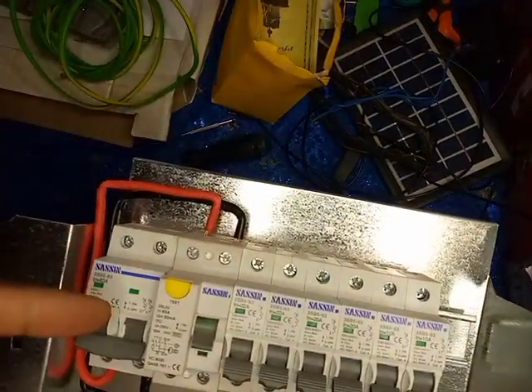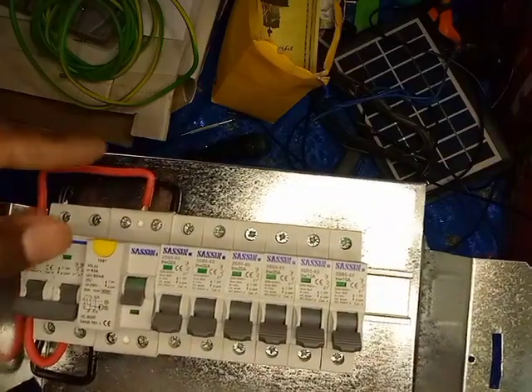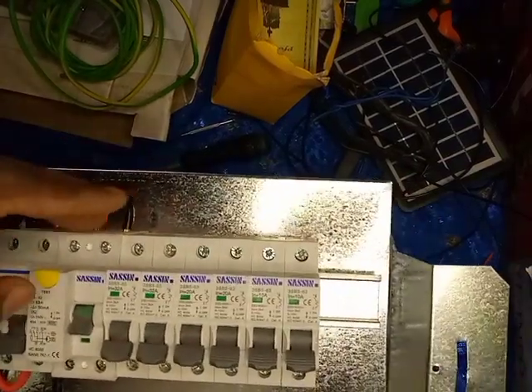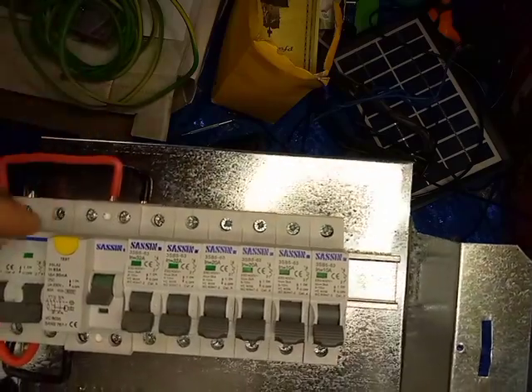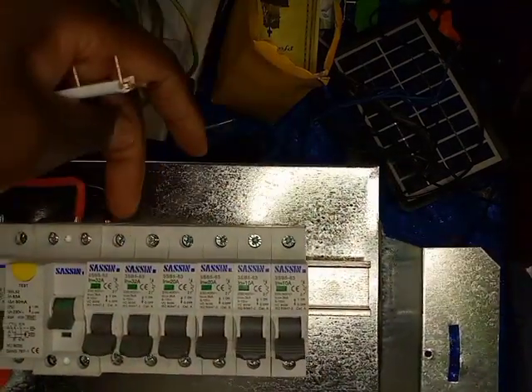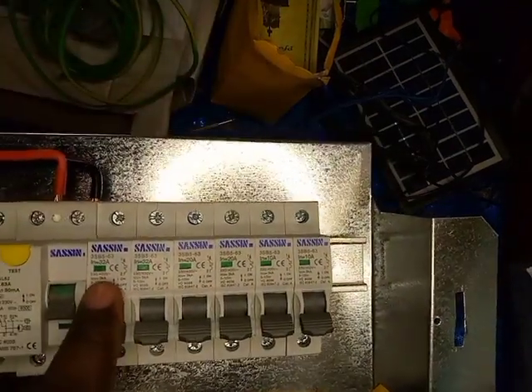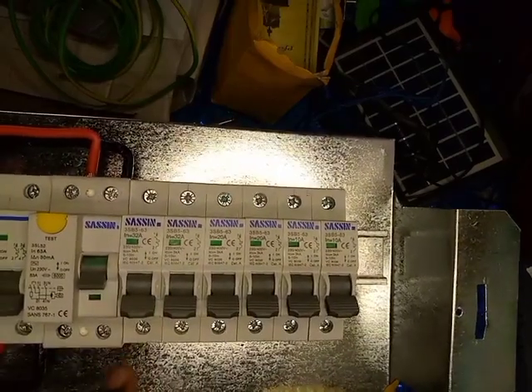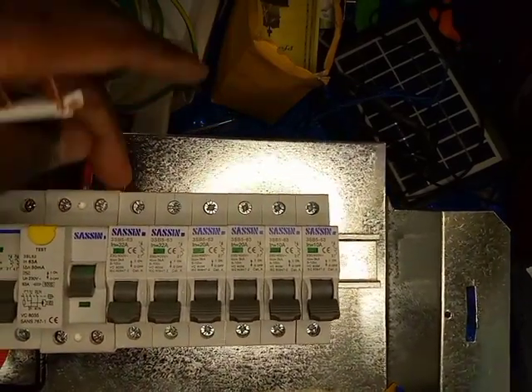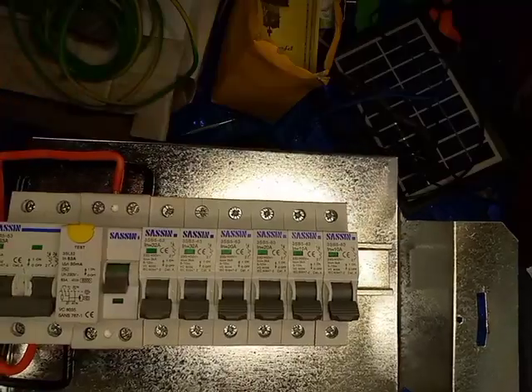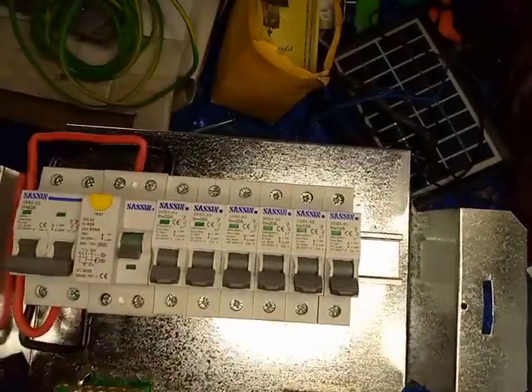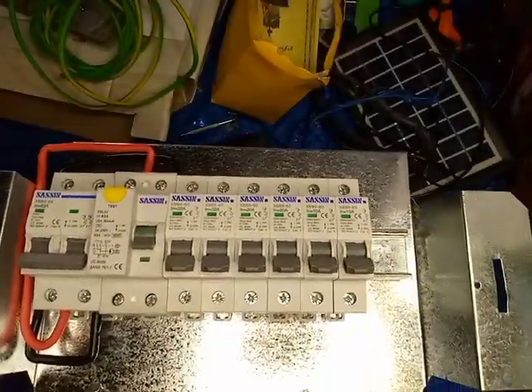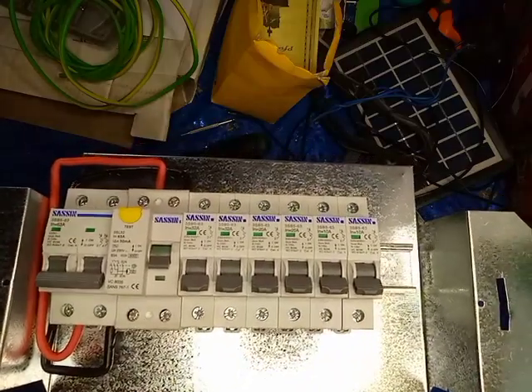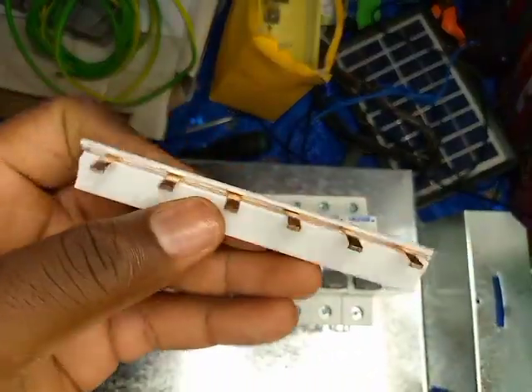Don't use smaller ones, because if you use a smaller wire, like a 2.5 millimeter wire, to jump around here where it's a 32 amp circuit breaker, you'll have to connect the bigger wire. Otherwise the current or voltage coming through will be much smaller than it's supposed to be. So make sure you use the correct type of wires or the correct size of bus bars.